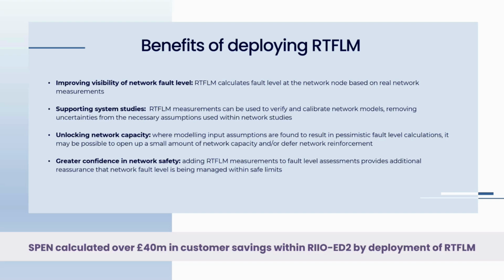And in terms of our business case for deploying these in ED2, I've calculated over 40 million in customer savings across ED2 directly from deploying real-time fault level monitoring and enabling us to defer network reinforcement. And finally, greater confidence in network safety. By adding real-time fault level monitor measurements to fault level assessments, it provides us with additional reassurance that network fault level is being managed within safe limits.